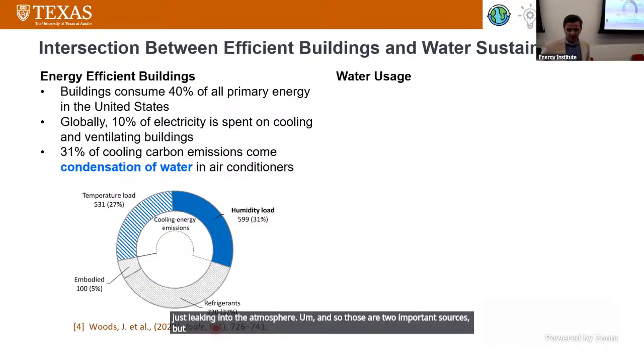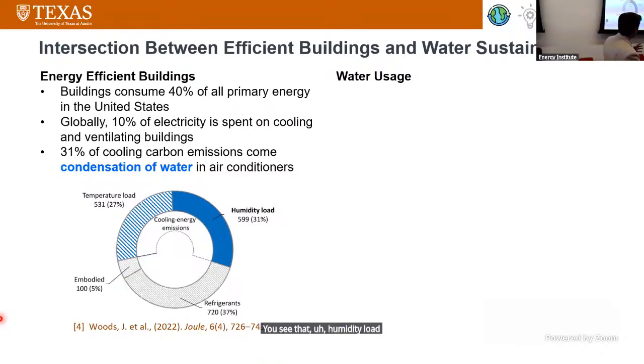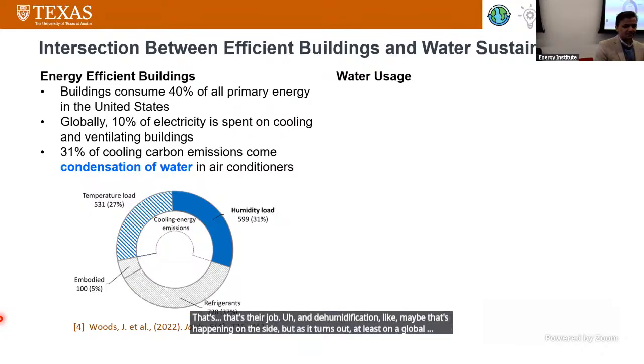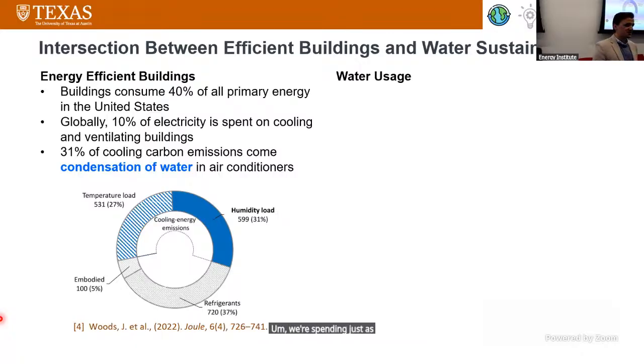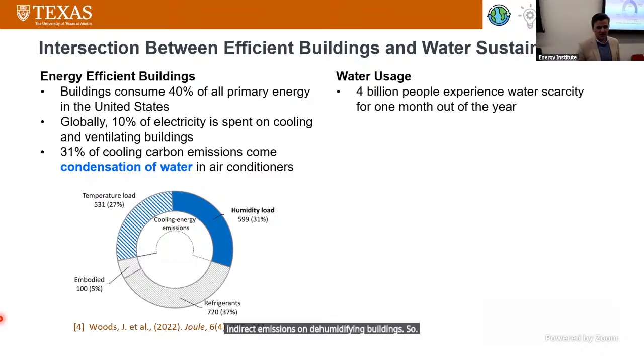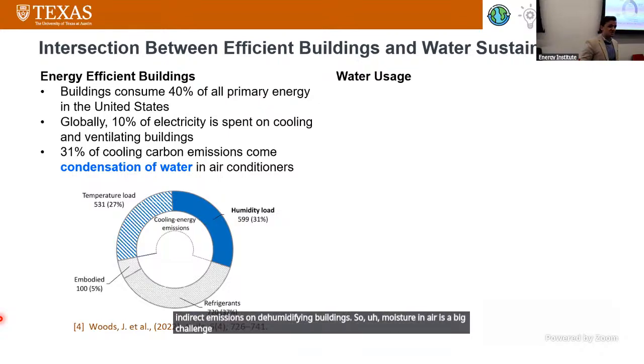But if we just look at the temperature load and the humidity load, humidity load is about 31% of total global emissions associated with air conditioning, whereas temperature load is only about 27%. That's interesting because if you don't think about air conditioning every day, you might just think air conditioners are there to cool the building, and dehumidification is happening on the side. But as it turns out, on a global average, we're spending just as much, if not more, energy - and thus indirect emissions - on dehumidifying buildings. So moisture in air is a big energy challenge for buildings.